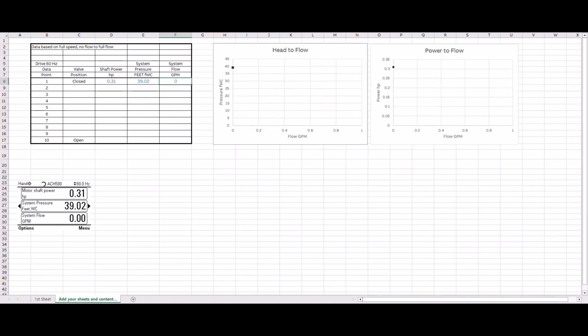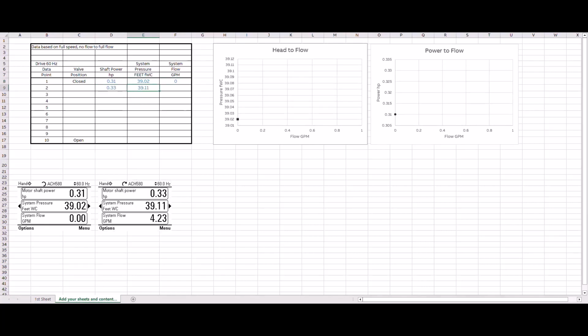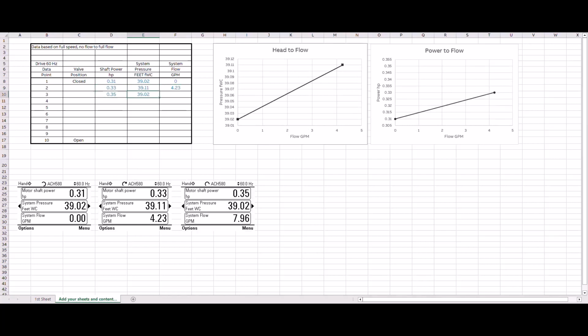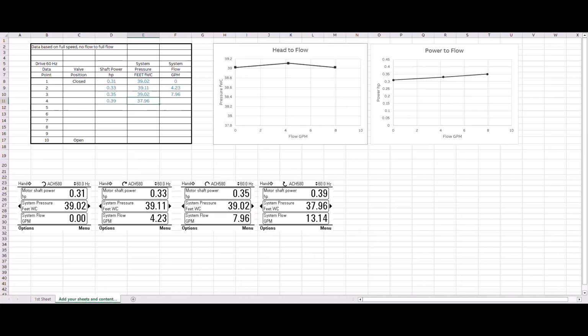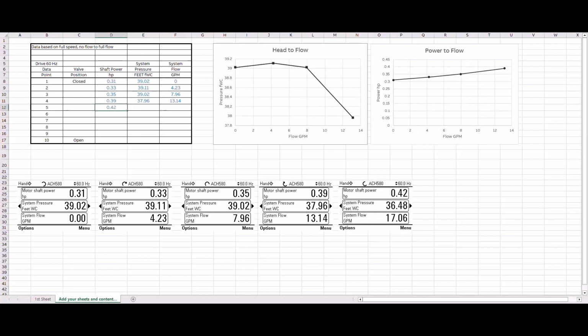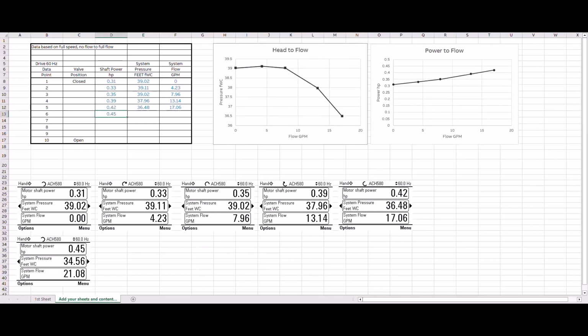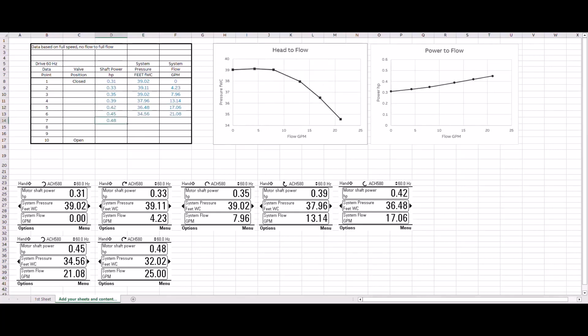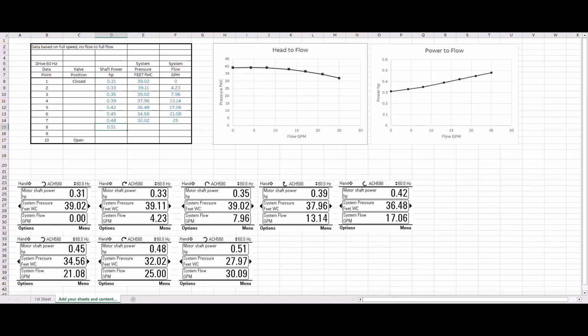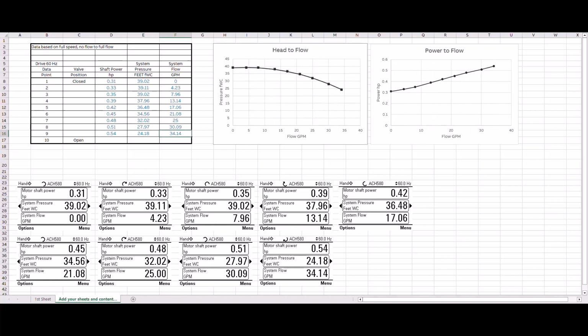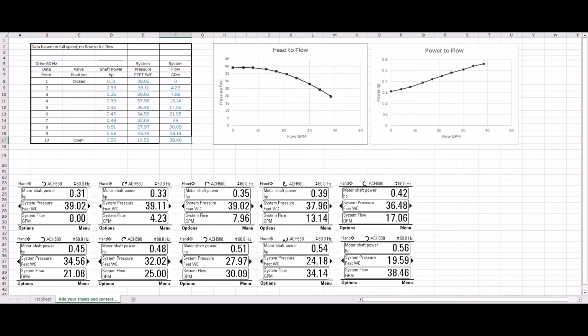The next information that we have is for data point 2. Then we have data point 3. And as we enter this information individually, we're going to start building up our graphs. We want to do this to make sure that we have a good system for sensorless pumping. Depending on the pump and motor combination, we need to have data points that allow the drive to do the calculations.